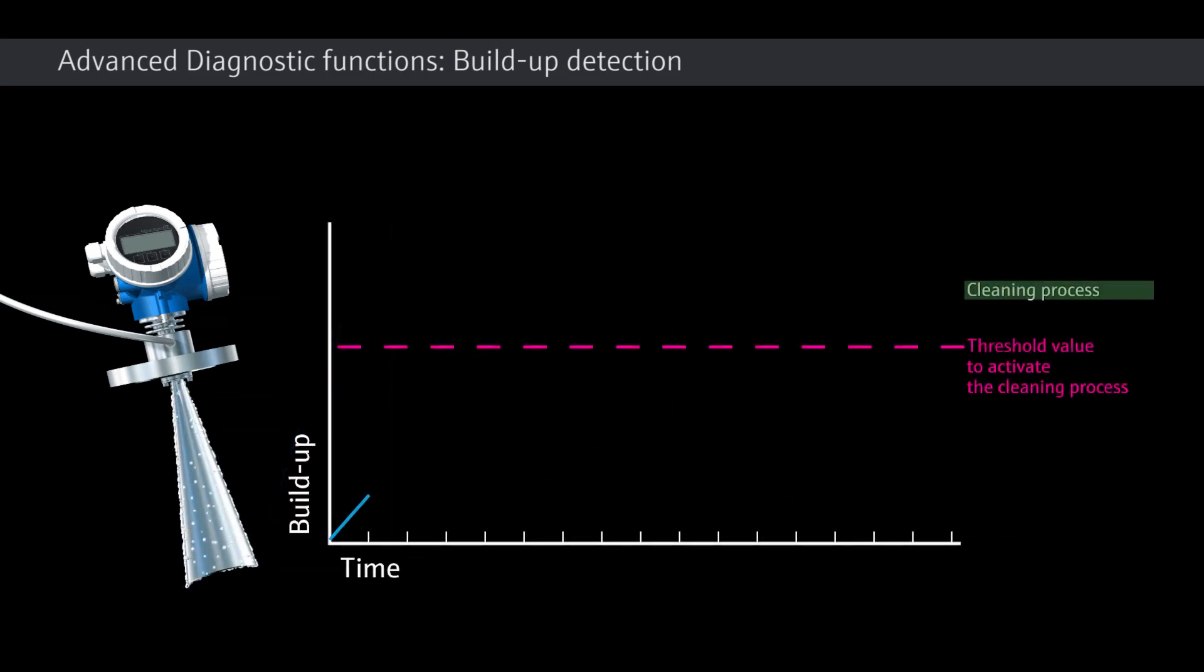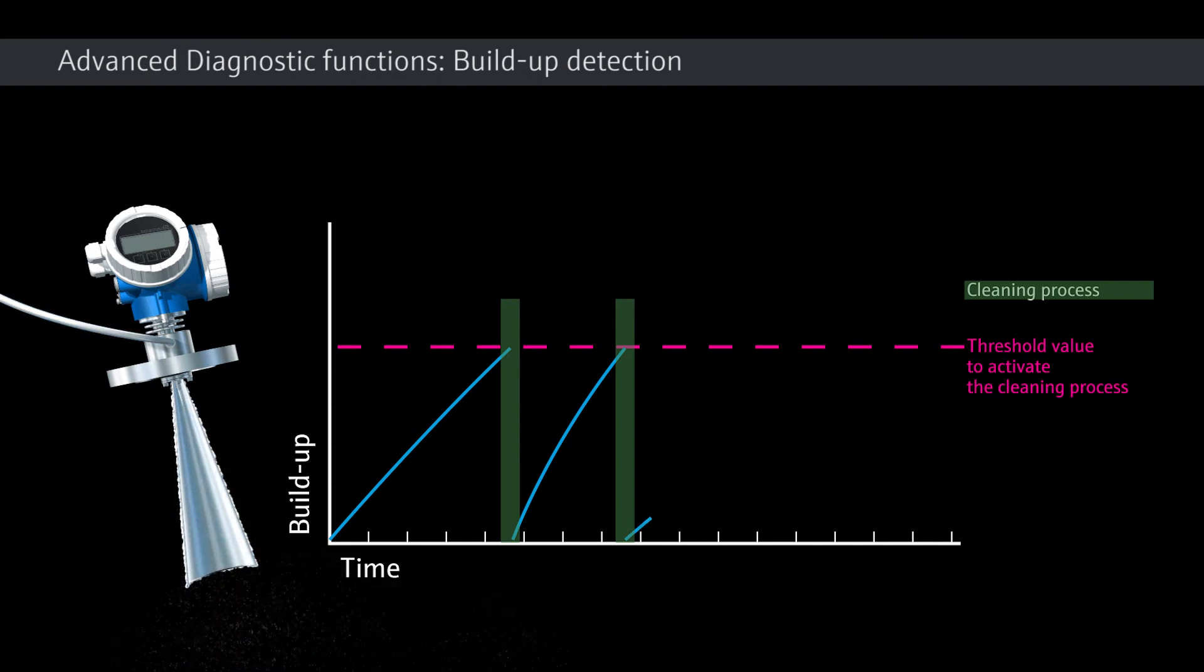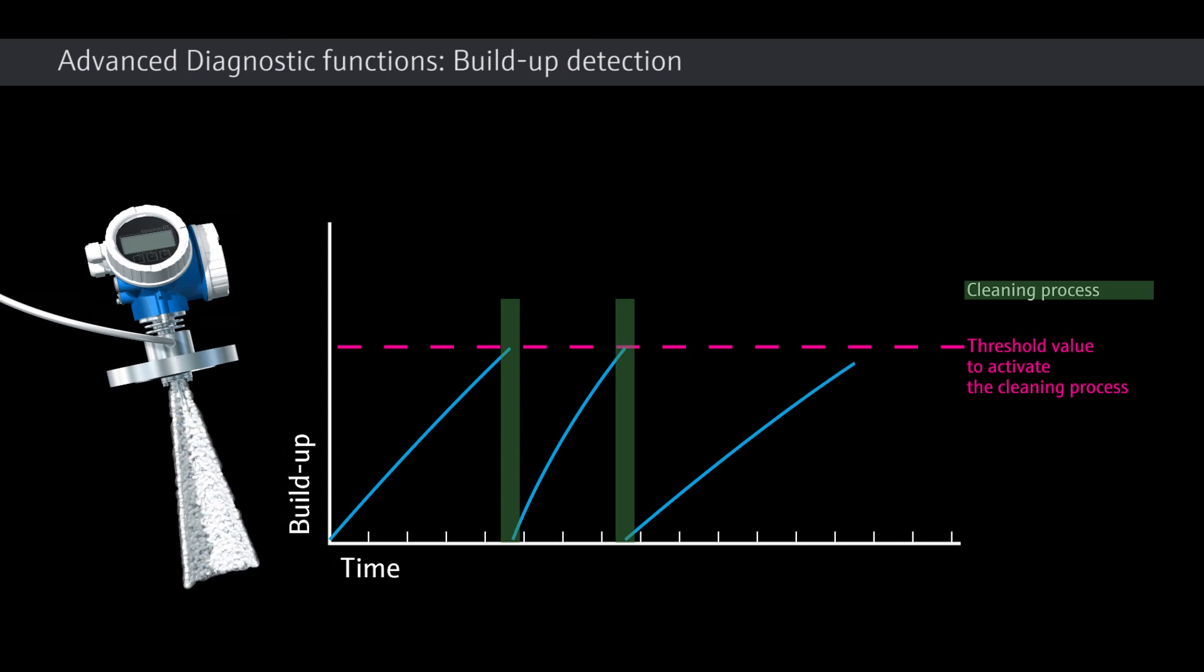This process diagnosis controls cleaning cycles in a very effective manner, since cleaning only takes place if buildup is actually present and a defined threshold has been passed. This avoids wasting compressed air and in addition increases the availability of the measuring point considerably.